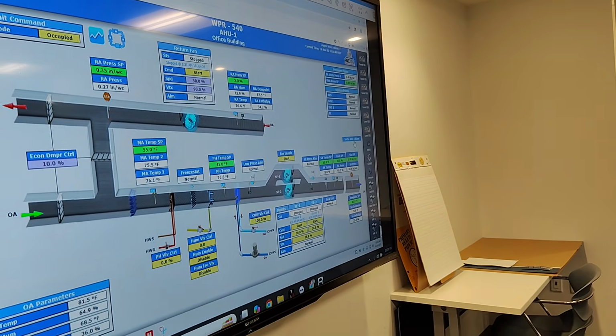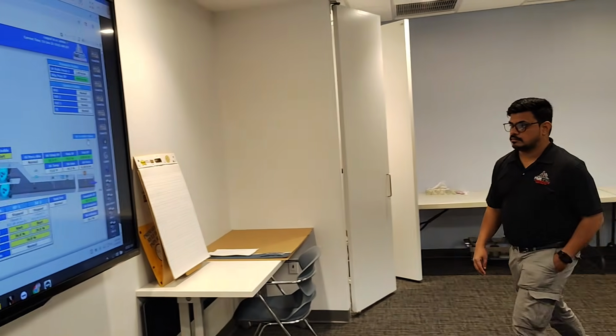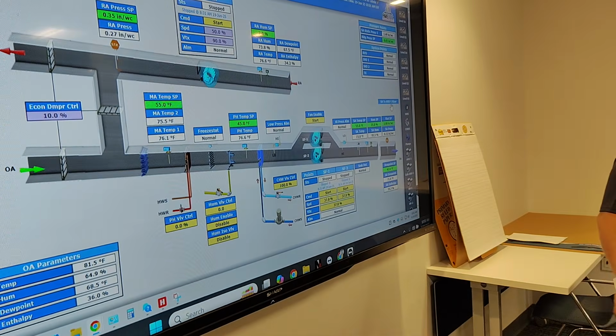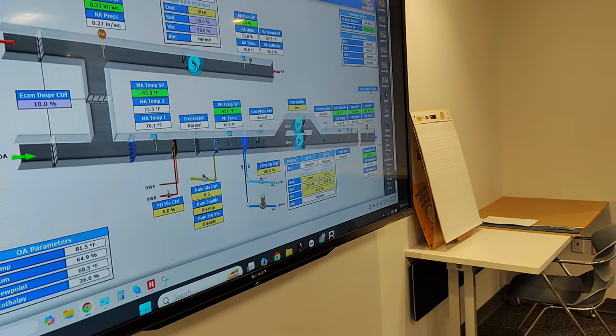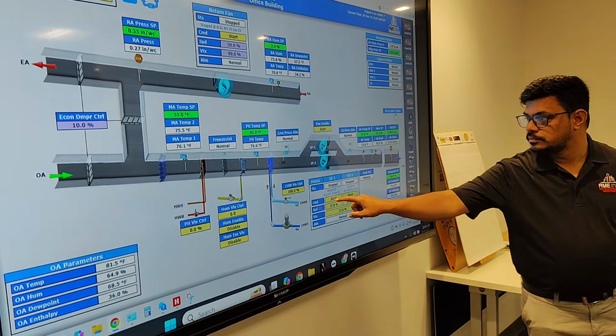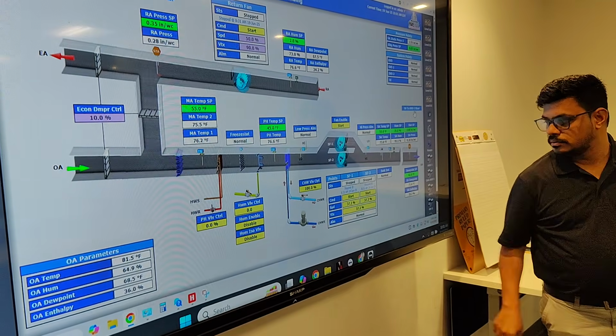So it's 36% ramping somehow, so it is trying to. Listen, where is the fan speed? Where is that? Down there underneath where it says start, 36%. Those two speeds, right? Dinesh, point to where it says stopped at status. So that's supply fan 1. Yep. And supply fan 1, supply fan 2. So that's the information about those fans. If it was stopped, it would say stopped.